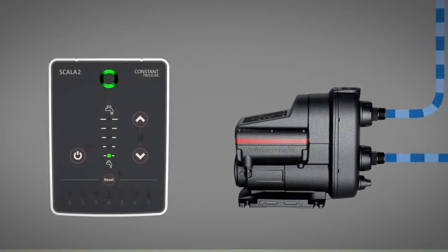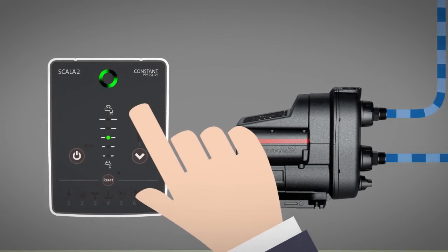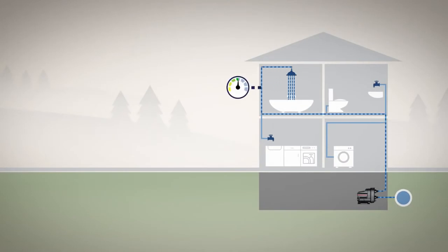For installers, this means that the setup process is quick and easy. Simply set the desired pressure level using the control panel and check the water pressure at the furthest tapping point, preferably a shower, as this is where insufficient pressure will be felt most directly by the homeowner.